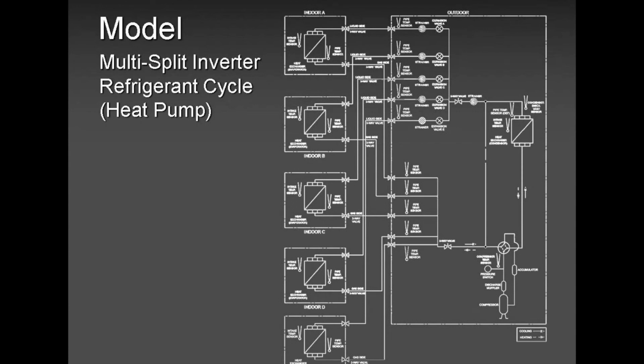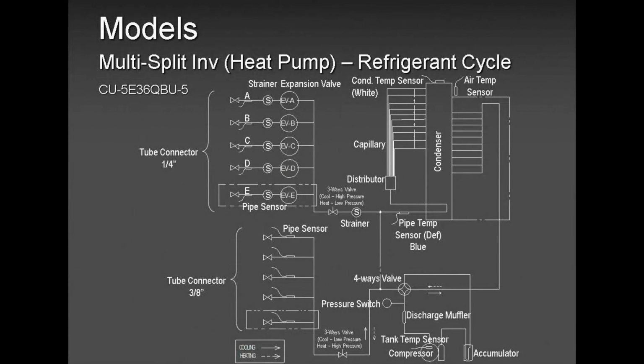10 feet is standard. Minimum is 10 feet. For this particular model, 82 feet per indoor unit is maximum. Okay, but other models, 10 feet still remains minimum, and chargeless. The unit has been charged for 25 feet, and as it crosses 25 feet, you need to add, depending on the model. So please remember, I don't expect you to absorb all this, but always refer to the installation manual that comes in the box. And again, if it's not clear with you, you are always welcome to give us a shout. Give us a call anytime. Doesn't matter, we will answer your call.